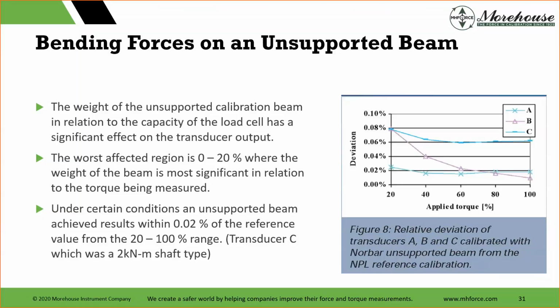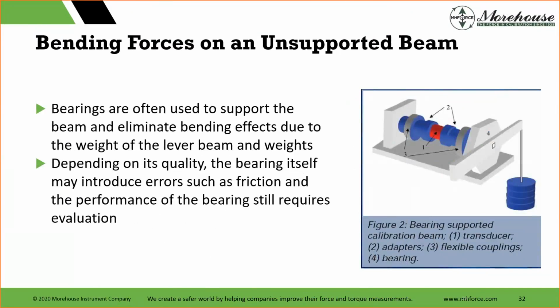And really important, a lot of the manufacturers will specify, for their torsion cells, what size beam to use with it. Now, how do we solve this? This setup is the best way: a bearing supported calibration beam, transducer adapters, flexible couplings, bearing. It's a much more expensive setup. Bearings are often used to support the beam and eliminate bending effects due to the weights of the lever beam and weights. Depending on its quality, the bearing itself may introduce errors such as friction, and the performance of the bearing still requires evaluation. So an air bearing, ceramic bearing, other bearings, you still need to go back and quantify them.